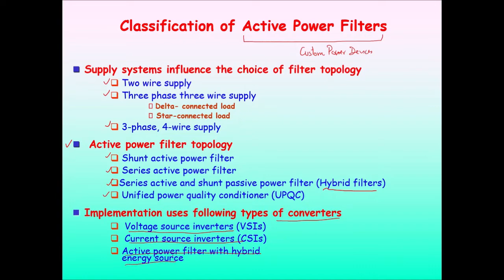So you can see here that the shunt active power filter is basically a voltage source converter, supported by a DC link and some filter components L or C to condition the output of this inverter to the desired value of current or voltage. And these currents together are such that the IS is perfectly sinusoidal and in phase with the voltage, or at the desired power factor with the source. So they are mainly used for distribution networks, to eliminate the harmonics due to the nonlinear load, any kind of unbalance, or for the compensation of the reactive power.